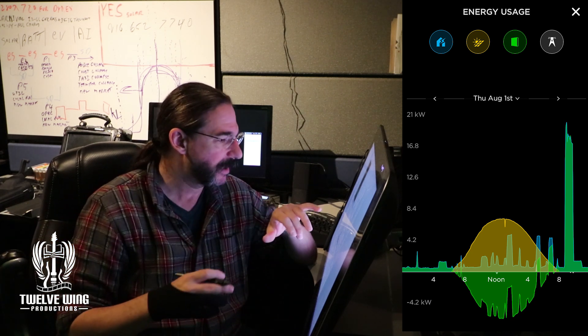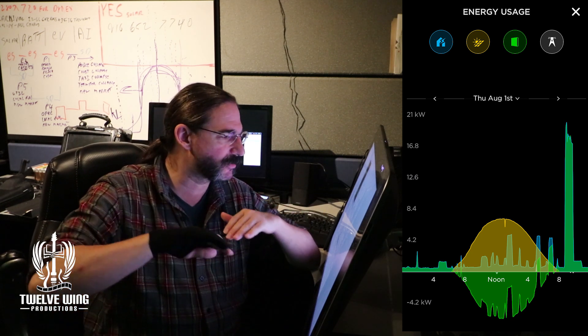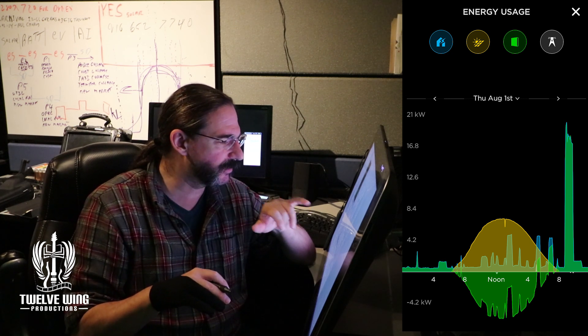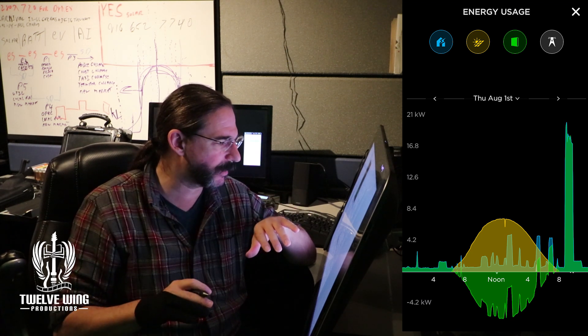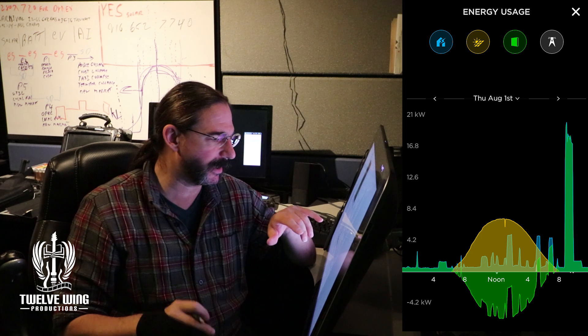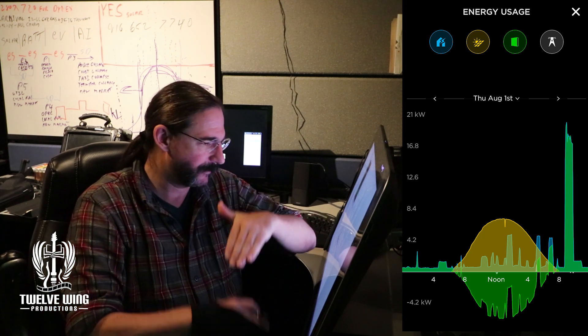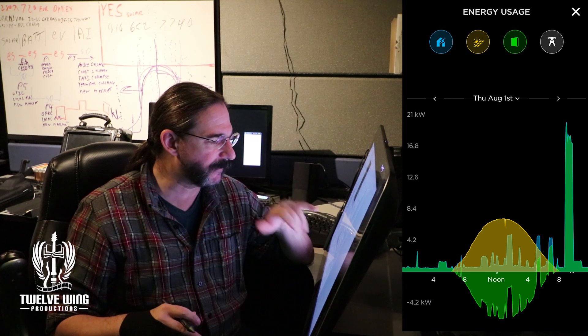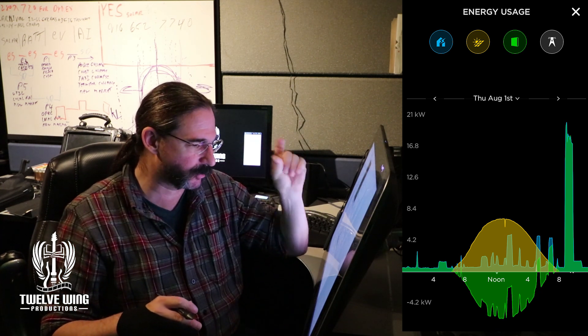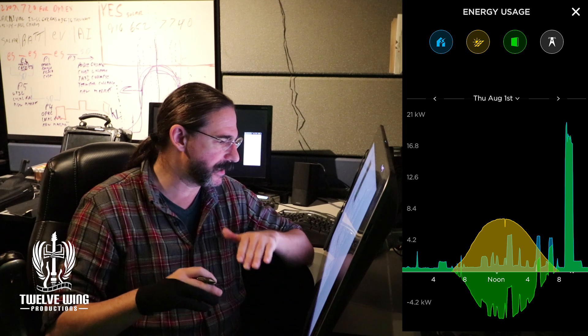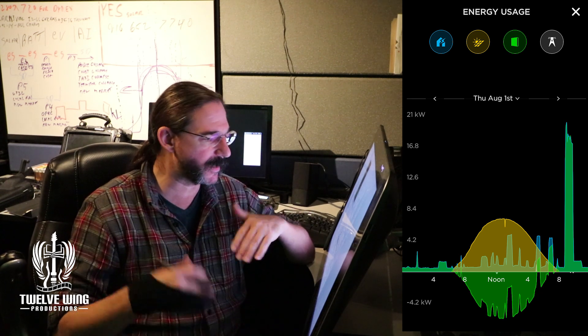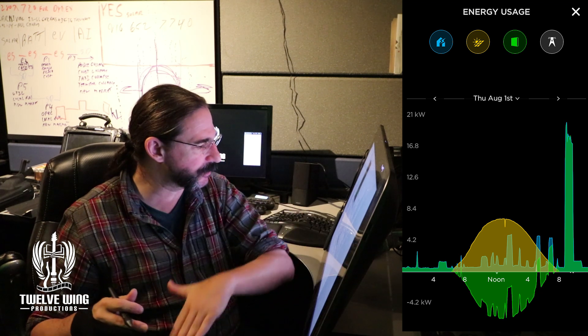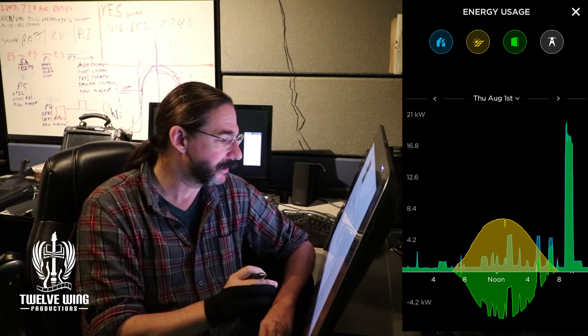If you look closely at the green that sits just below it, you'll notice that the green part is ramped up and to the right. And so then if you look at the solar graph, you'll see that the solar contribution goes down and to the right exactly mirroring what's going on with the green. So then if you take a look at the amount of the solar contribution that's above that zero line, you'll be able to compare that to the volume and the volume exactly matches the difference between that green top and the blue load. This shows us that you're seeing a combination of how the air conditioning load is split up with part of that load coming from the solar and the remainder coming from the battery. And so then as the solar contribution decreases, the battery ramps up to compensate for the combined load.